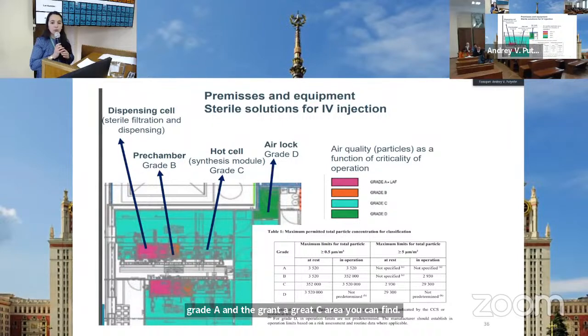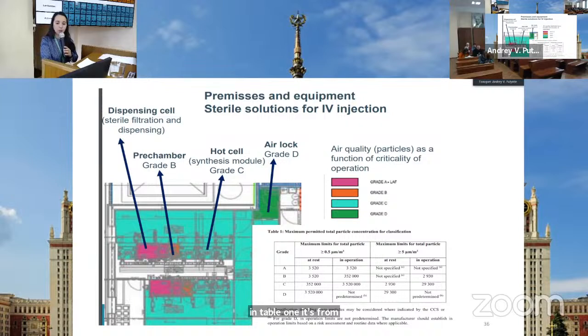For sterile solution for intravenous injections, what type of equipment do we use? Dispensing cell, it's a class A area; pre-chamber, grade B area; a hot cell, grade C, where we can put the synthesis module; and an airlock where the personnel change clothes and go in. It's grade D, and then grade C area. In Table 1, from the GMP rules, we can find the requirements for each class.